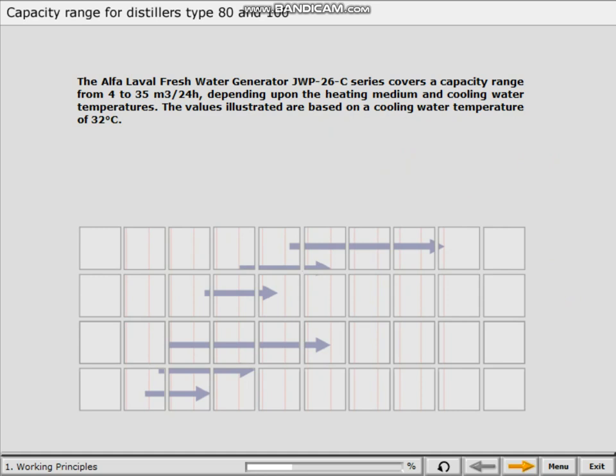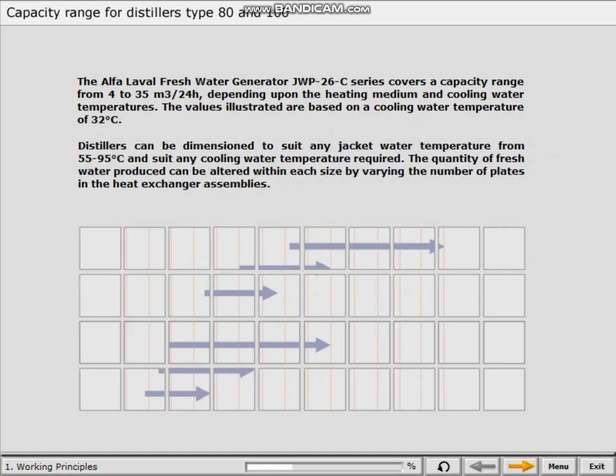The Alfa Laval freshwater generator, JWP-26C series, covers a capacity range from 4 to 35 cubic meters per 24 hours, depending upon the heating medium and cooling water temperatures. The values illustrated are based on a cooling water temperature of 32 degrees Celsius. Distillers can be dimensioned to suit any jacket water temperature, from 55 to 95 degrees Celsius, and suit any cooling water temperature required. The quantity of fresh water produced can be altered within each size by varying the number of plates in the heat exchanger assemblies.